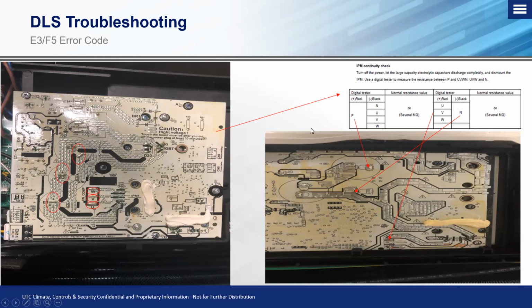Now you'll see on the actual flow chart that it says about several megohms. Typically, I give a range of about 4 to 8 megohms. Once you start reading above that, it gets a little bit excessive. Then you can confirm there might actually be an issue within your drive board, or it's not allowing the correct amount of DC voltage to be outputted either to the W, V, and U terminals for the compressor or to the fan motor itself.